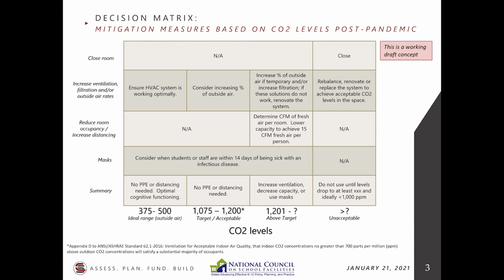But again, in a classroom, COVID isn't the only reason we ventilate. We ventilate to bring down levels of VOCs and so many other things as well, and for aesthetics and odors and whatnot. Some of the air cleaners have a thin layer that's carbon coated, but they're not intended to last long. So the carbon isn't going to be highly effective in removing odors over a prolonged period of time. So I'm telling you, there are options.